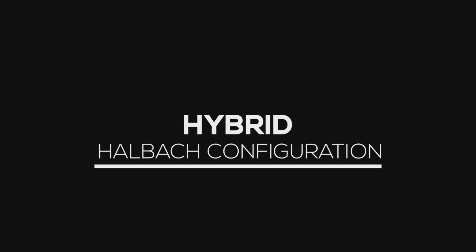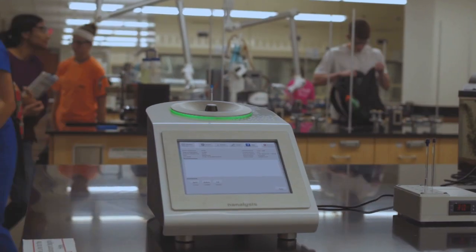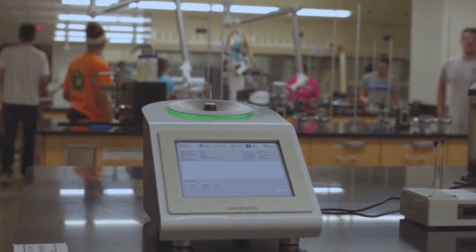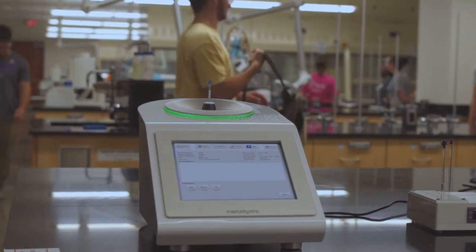We used newly available rare earth magnets and we use them in what we call a hybrid Halbach configuration. We felt that the market really wanted an NMR spectrometer in a single unit that could be moved from laboratory to laboratory, both in a teaching laboratory situation and also in a routine quality control or research setting.